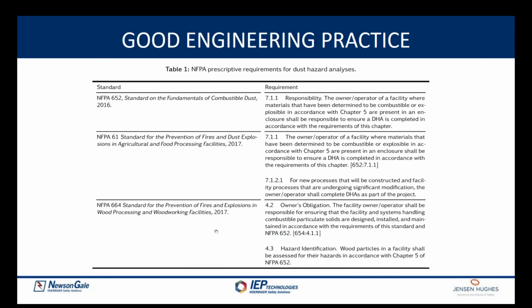These are specific excerpts from three NFPA standards that relate to the biomass handling and producing industry, and they basically show the requirement for a DHA and the relevant chapters and sections that talk about that. NFPA 652, in the annex material, will actually give you an example of what constitutes an acceptable and defensible dust hazard analysis, or DHA.